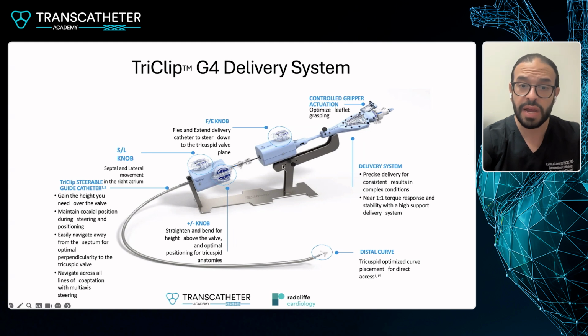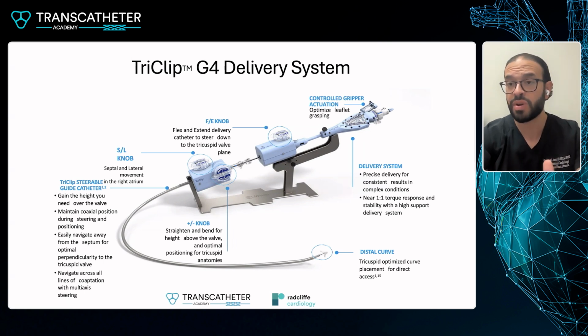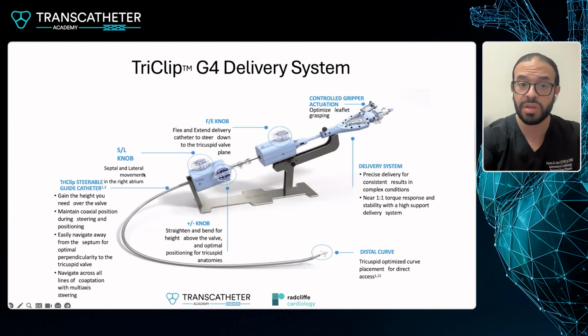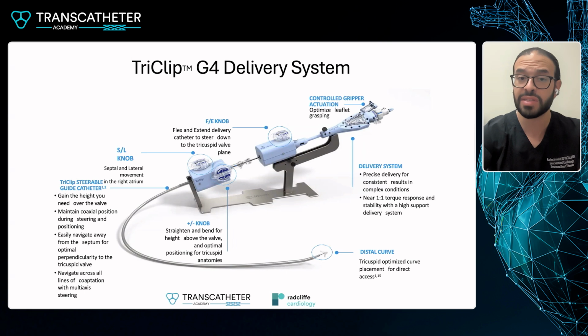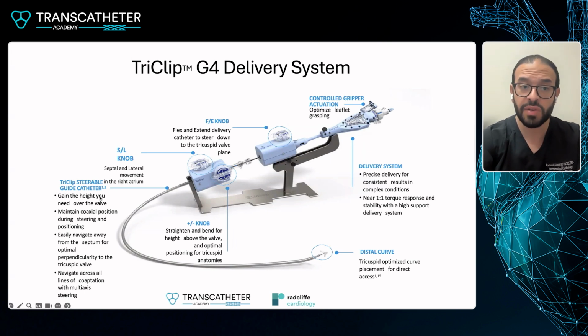This is the area where you can bring in the device from the atrium down to the ventricle using the flex and extend knobs on the delivery catheter to steer down. What's important and what's different about the TriClip device as compared to the regular mitral clip device is the septal and lateral movement knob, which allows the device to go more septal or lateral, as compared to the mitral clip device that doesn't have that knob. And then finally, we have the steerable guide catheter at this end, which is meant to have a plus and a minus knob to straighten and bend, to add height above the valve and vice versa.